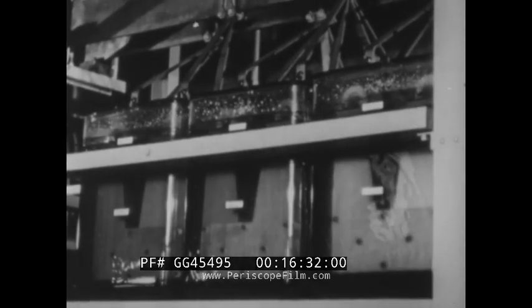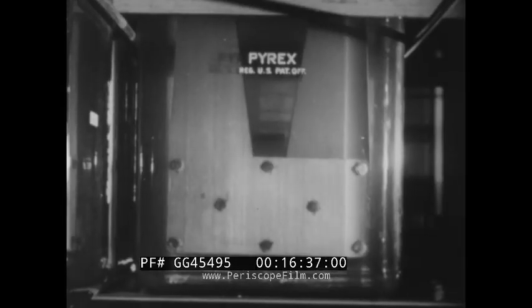Counter-EMF cells are a vital part of most storage battery plants. The plates are of stainless steel and the solution is sodium hydroxide. Note the correct water level. A layer of oil covers the top of the solution to prevent loss of solution as spray when gassing, and to prevent solution contamination by the carbon dioxide in the air. Counter-EMF cells act as a resistance in the circuit, and are used to reduce the voltage in certain plants during normal operation and in others during boost charge only.